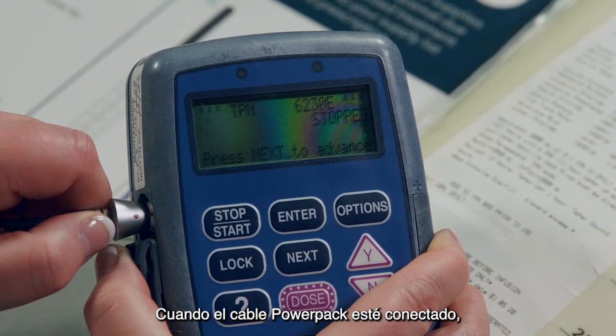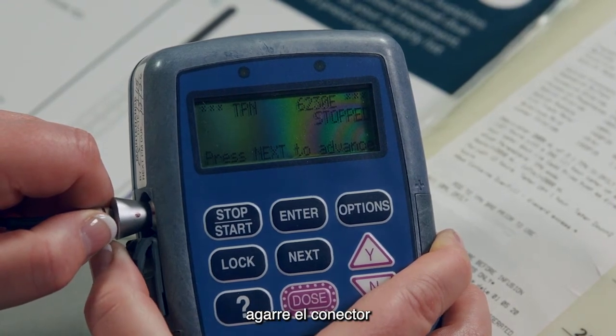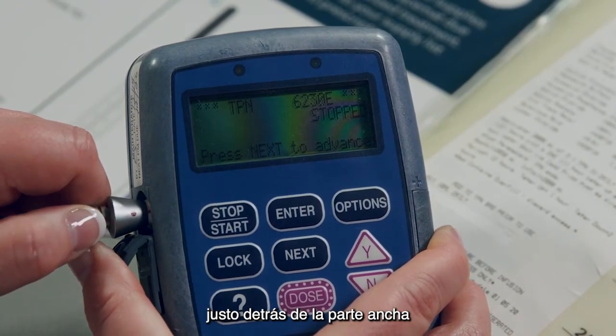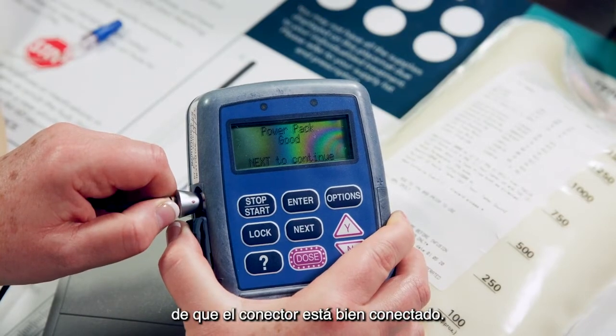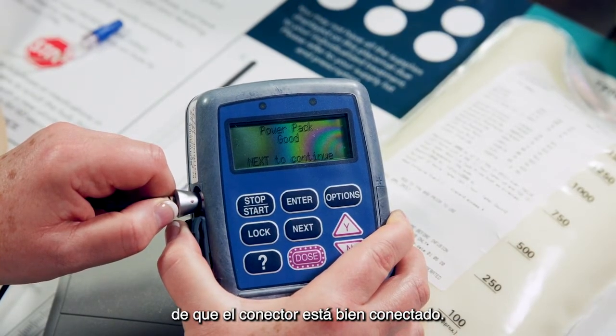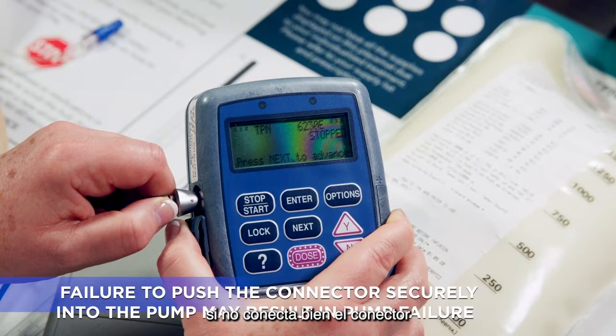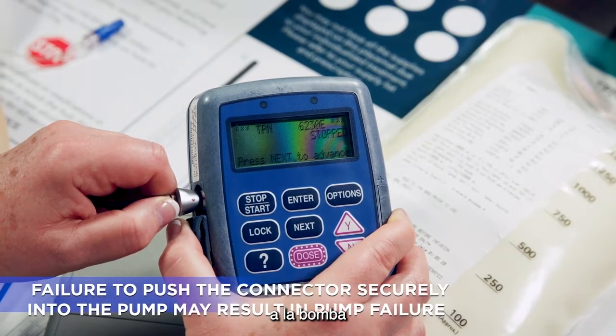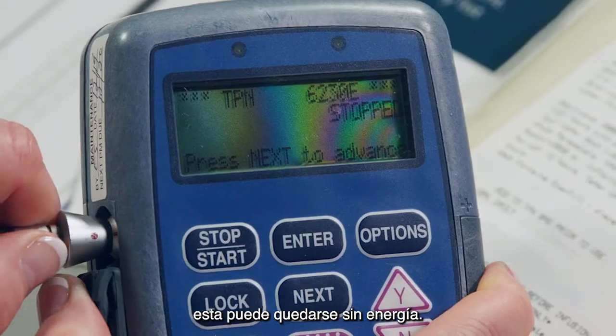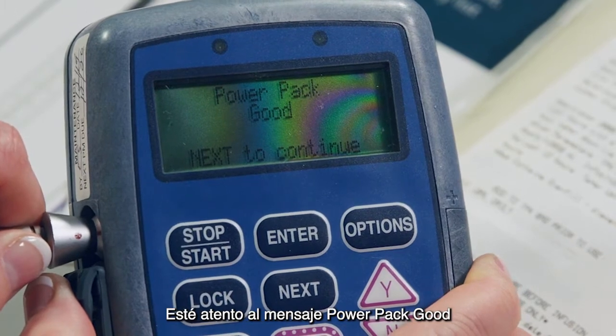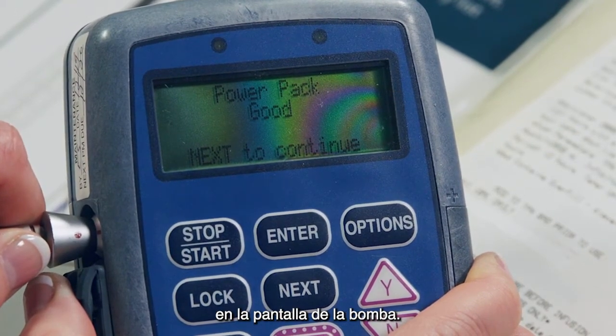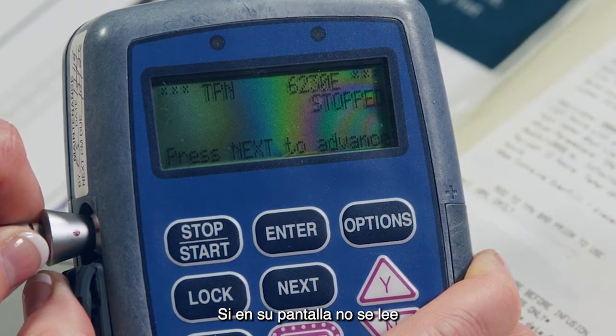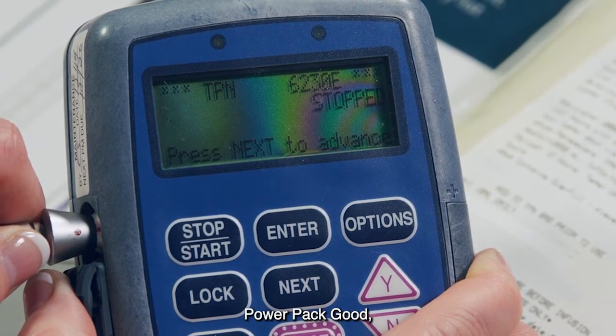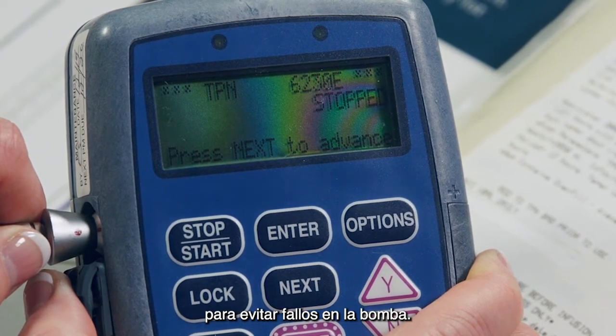Once the power pack cord is connected, grasp the connector directly behind the flared portion and lightly pull to ensure the connector is securely attached. This is important because failure to push the connector all the way into the pump may result in loss of power. Watch for the message Power Pack Good on your pump's display. If your display does not read Power Pack Good, double-check the connections to prevent pump failure.